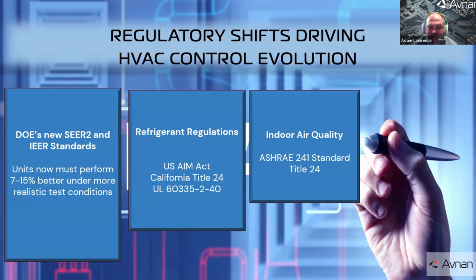Secondly, refrigeration requirements. The U.S. AIM Act and California Title 24 are phasing out high GWP refrigerants. New systems must use low GWP A2L refrigerants, which are mildly flammable. That triggers safety requirements under UL 60335-2-40, including built-in leak detection, ventilation triggering, and fail-safe shutdown modes. Control boards must now include sensors, logic, and fault recovery built to handle these new refrigerant realities.